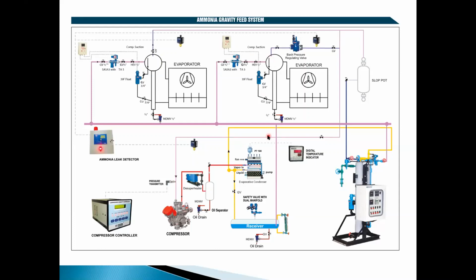When we have multiple applications and multiple temperatures, depending on our requirement, we can have a differential pressure regulation system. Having a back pressure regulator helps us maintain two different temperatures in one common suction. For example, we have an ice plant where ice production is at minus 10 degrees centigrade and ice storage at plus 2 degrees centigrade. Your compressor can work at minus 10 and produce the ice, and also maintain plus 2 in your cold storage room by using a back pressure valve or an evaporator pressure regulating valve.